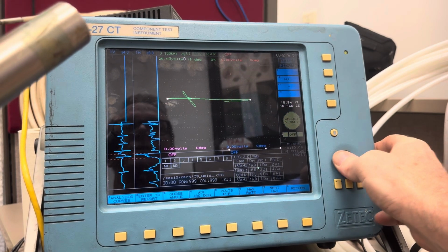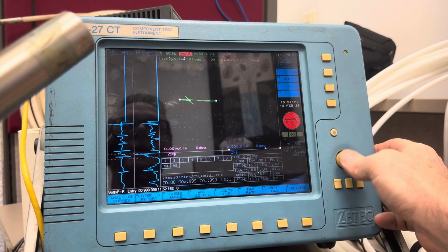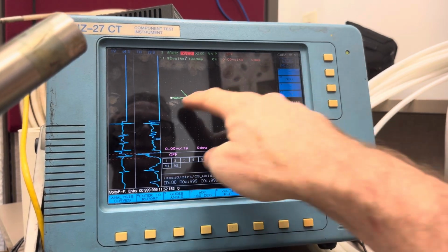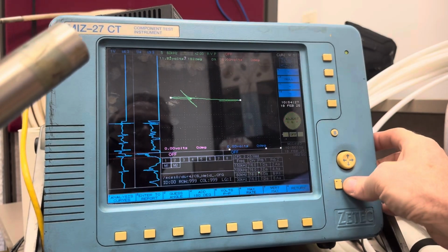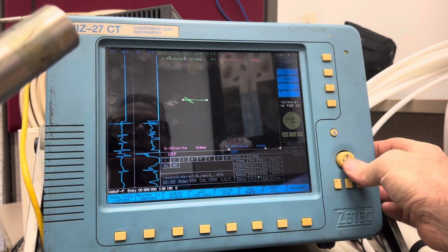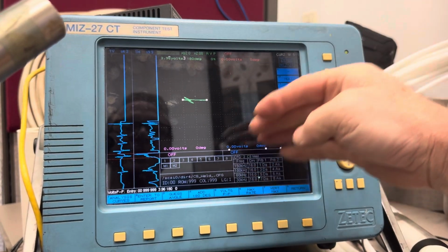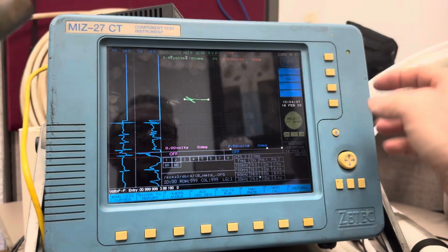Then we'll go over here to channel 5. It spans down a little bit on that one there. There's your 180, and here's your dent again, 182 degrees. What do you think it's going to be on channel 7? 180 degrees. So as we stepped through the frequencies, the dent didn't rotate. It just stayed pretty much flat.